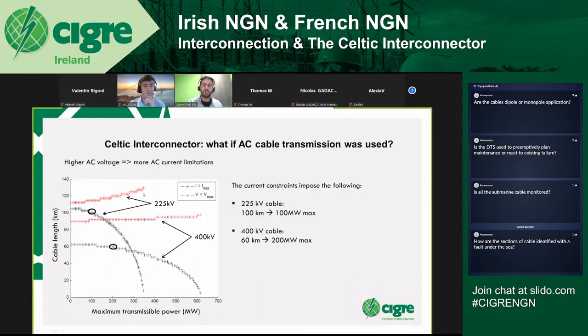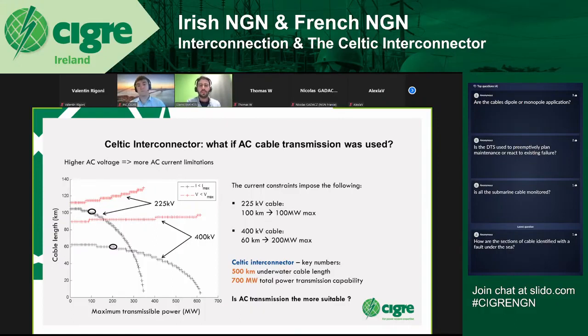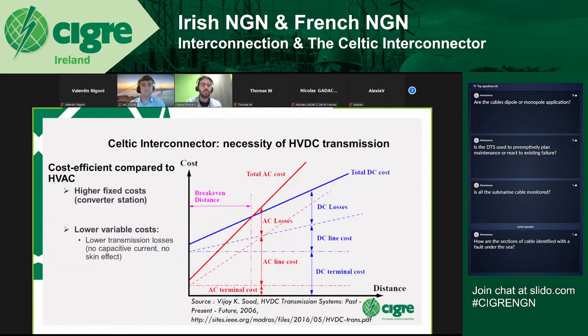If you dig into the Celtic Interconnector project, some key numbers are that we have 500 kilometers of underwater cable length, not even counting the onshore cables, and we want a total power transmission capability of 700 megawatts. So it's clear here that AC transmission cannot be used for this project.